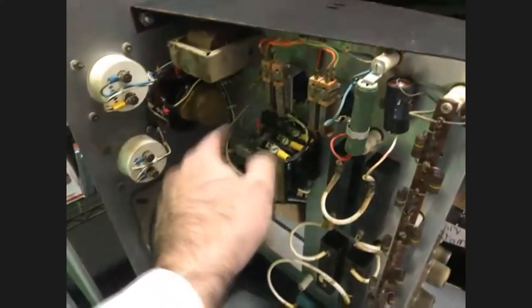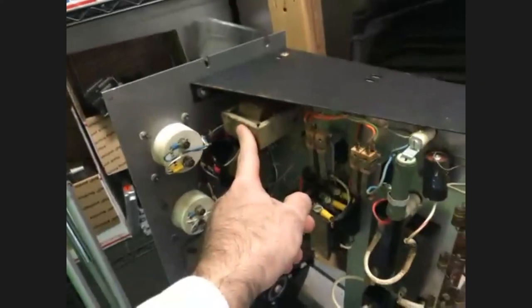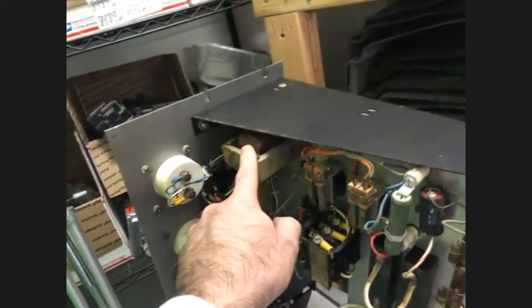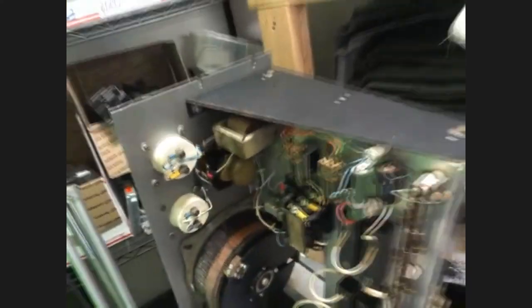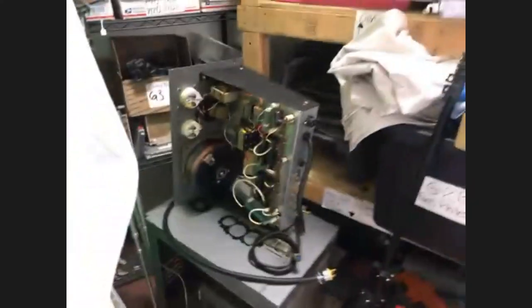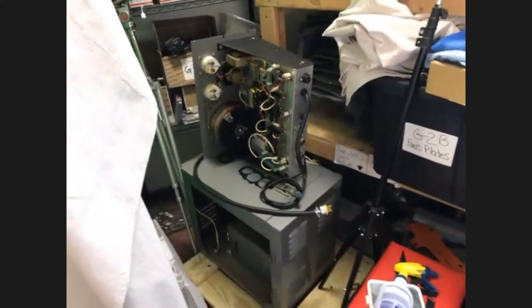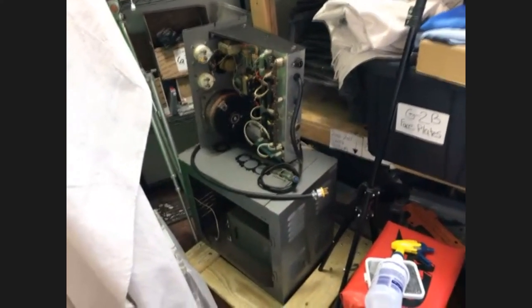So I think this is the interlock. There's a problem — that transformer is blown out. It's a 12 volt transformer, so the interlocks are not working. We could either replace the transformer or just override the interlock. It's something we're considering.